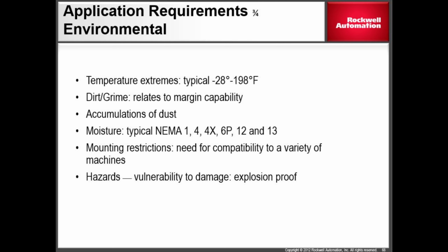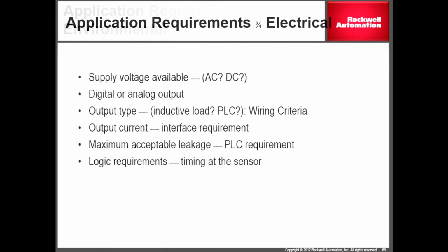Are there any mounting restrictions? Do I need compatibility to a variety of machines? Is it a hazardous location? Maybe an explosion-proof sensor is required. Supply voltage, 120, 24, 12. Is it AC or DC? What type of output? Is it digital, just a discrete on-off, or is it an analog, where I need a 4 to 20 milliamp or maybe a 0 to 10 volts on the output? What type of device am I trying to control with that?